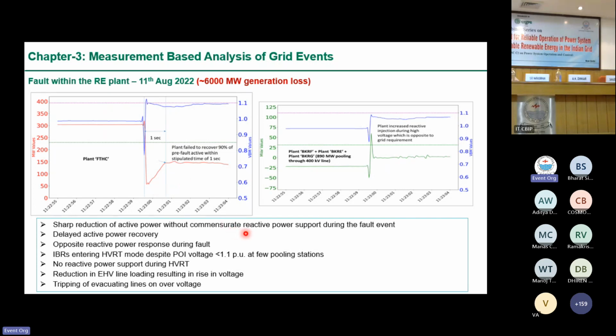This delayed recovery of active power, coupled with almost no or opposite reactive power support, resulted in high voltage immediately after the fault clearance, which then caused most of the IBRs to enter into HVRT mode. Now at some of the pooling stations, the voltage was not even above 1.1 per unit, but the IBR level voltage might have crossed 1.1 per unit. So the IBRs entered into HVRT mode, which led to further reduction in active power generation. Then because the long evacuation lines were getting lightly loaded, the voltage increased further, which resulted in more IBRs going into HVRT mode, and then ultimately tripping off the generation, as well as the tripping of evacuation lines after 5 to 6 seconds because of the stage 1 over voltage protection operation.